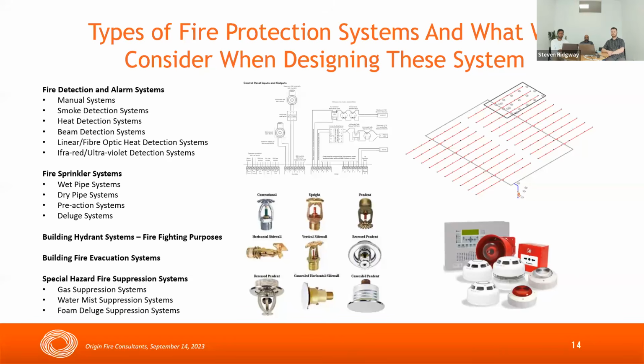In a particular building where the city's water supply cannot meet that demand, there's a need for diesel and electric pumps to ensure adequate pressure for the sprinklers to operate. Fire sprinklers can sometimes be required on the external facade of a building to cater for exposure risks from other buildings or other fire hazards such as transformers. We need to perform complex hydraulic calculations to determine the correct pipe sizes and lengths and the reticulation of pipework within a building, just to ensure they're within certain design parameters.